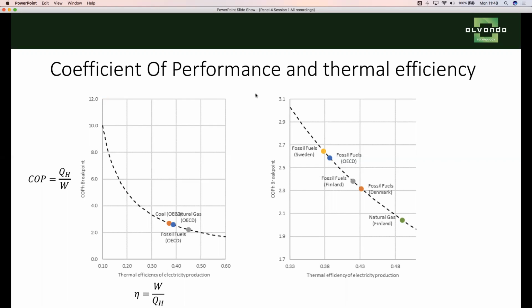Below that, maybe it just makes sense to burn the fuel directly in the boiler. If we look briefly at the graph on the left side, we have this dotted line which represents the break-even point where you have to be at a COP higher than the dotted line, depending on the thermal efficiency of your electricity production.